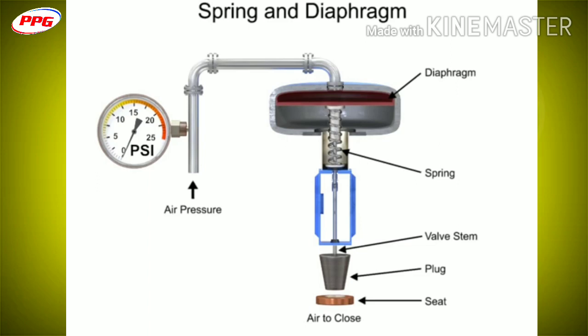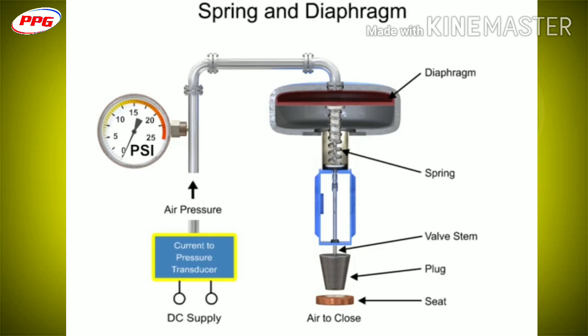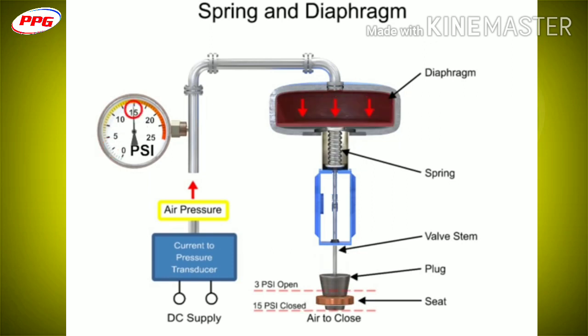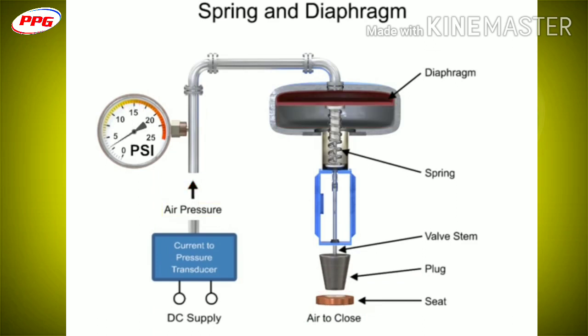To vary the position of the restrictor and flow through the valve, a current to pressure transducer can be used to provide a 3 to 15 PSI signal to the diaphragm. At 3 PSI, the valve is maintained open, and at 15 PSI, the valve is maintained closed. Pressures between the 3 to 15 PSI range proportionally change the flow of the valve.